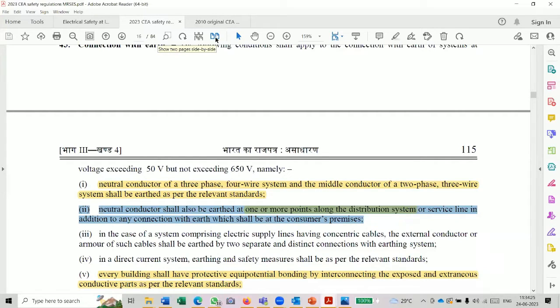What can consumers do? They just want to have their equipment safeguarded, have their life safeguarded. They fear. I can say that at least 90% of the consumers are reluctant. They can't connect that extra terminal with the supplier's terminal because they don't know what is the arrangement of the supplier's network, whether they have interconnection at the substation, whether they have provided PME, whether they have provided multiple earthing of the neutral conductor. These are totally alien to the consumer. That's why the standard places the responsibility with the supplier. Though we have to make the supplier aware as well, in order to avoid any hazard at the consumer premises.